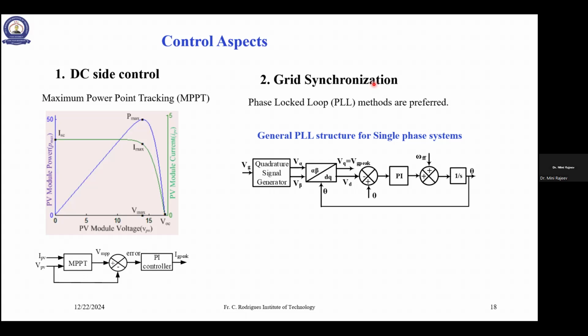If there is a difference, there will be circulating currents, and the grid will not get affected by that. What will get affected is our inverter, the devices and capacitors in the inverter. So we need to synchronize with the grid. That means when you are generating the voltage, we should make sure that it is the same as the grid voltage and the frequency is the same as the grid frequency. There are many methods for that. The most commonly used method is the phase locked loop method, PLL.